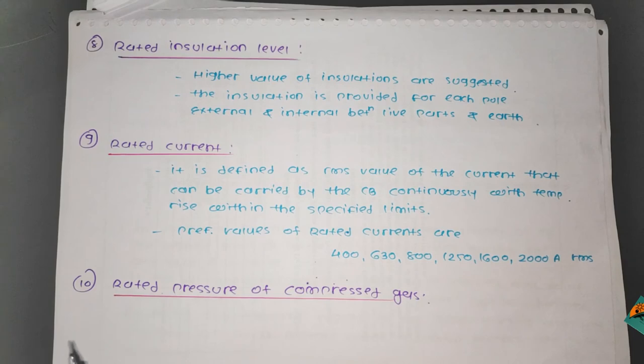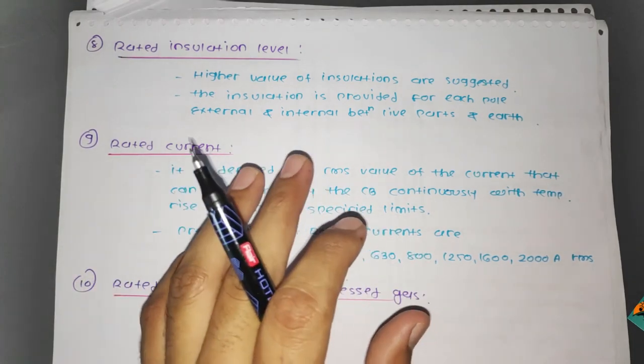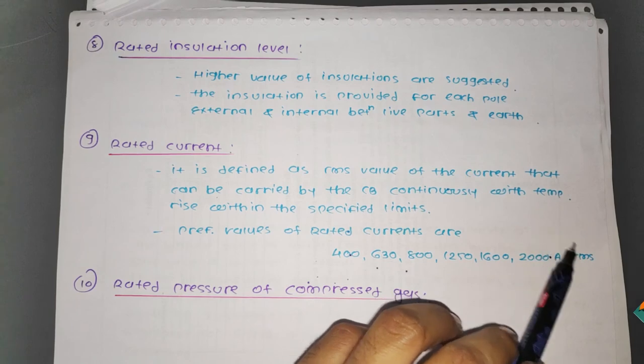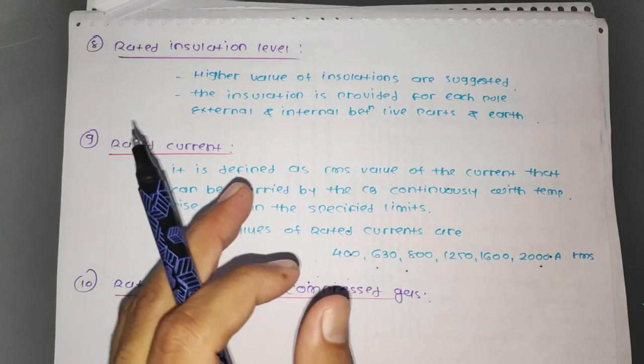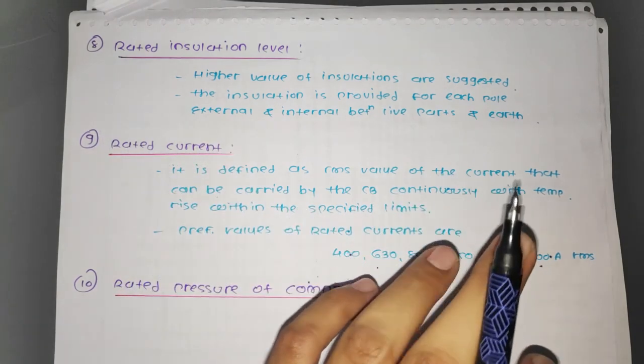Another rating is rated current. It is defined as the RMS value of the current that can be carried by the circuit breaker continuously with temperature rise within specified limits. Preferred values of rated current are 400, 630, 800, up to 2000 amperes. The rated current is checked by carrying out a temperature rise test, and current-carrying parts along with contacts are designed based on temperature rise. High conductivity material must be used; if low conductivity, cross-section must be increased.